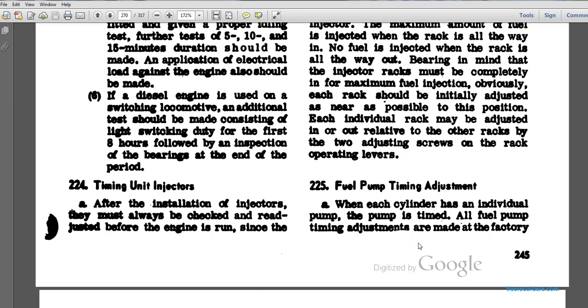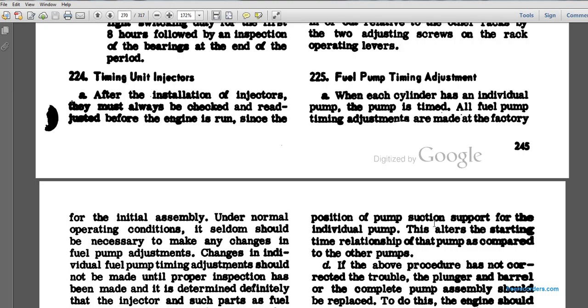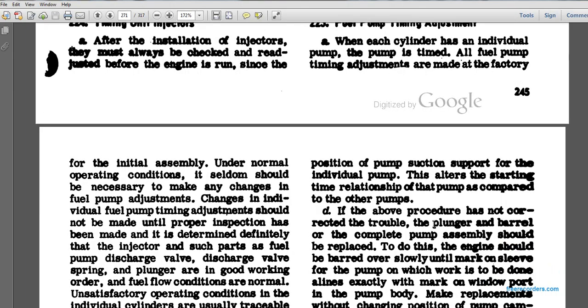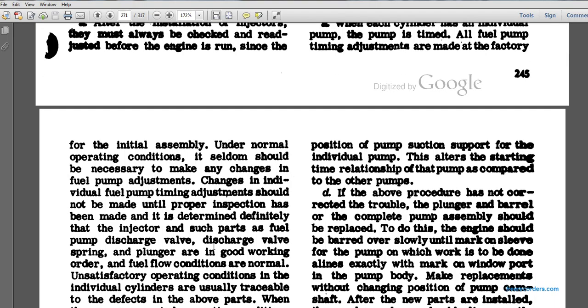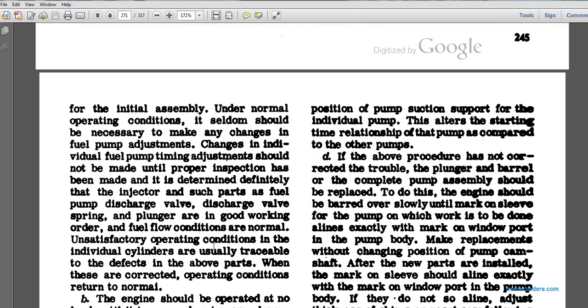225. The fuel pump timing adjustment. When each of the cylinders has an individual pump, the individual pump is timed. All fuel pump timing adjustments are made at the factory for initial assembly under normal operational conditions. It is seldom necessary to make any changes in fuel pump adjustments, and changes in individual fuel pump timing adjustments shall not be made until proper inspection has been made and it is determined definitely that the injector and such parts as the fuel pump discharge valve, the discharge valve spring and the plunger are in good working order and the fuel flow conditions are normal. Unsatisfactory operating conditions in individual cylinders are usually traceable to defects in the above parts. When these are corrected, operating conditions return to normal.